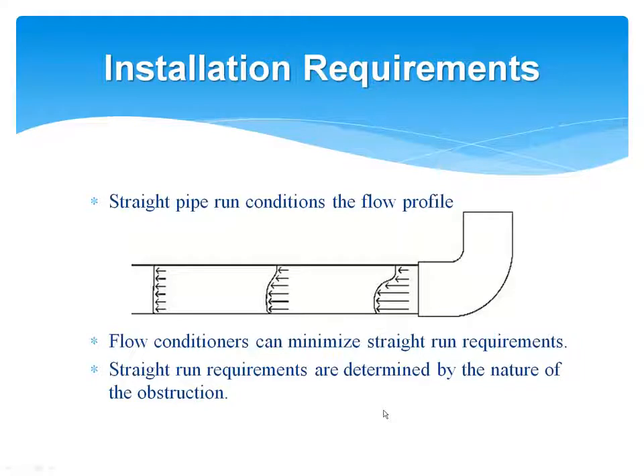Talk a little bit about installation requirements. Most steam meters like to have developed flow entering the meter location. Straight run of pipe is what conditions the flow into that developed flow profile. Note that there are flow conditioners that can be installed to minimize the amount of straight run requirements, and also that the straight run requirements really are dependent on what type of obstructions are upstream.